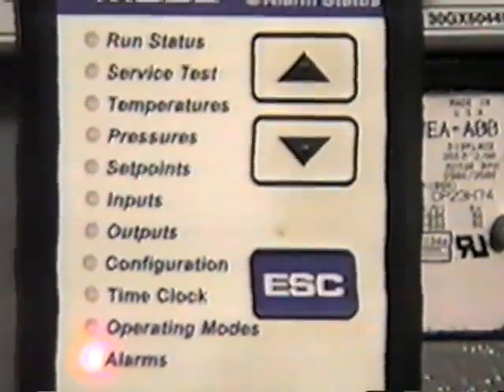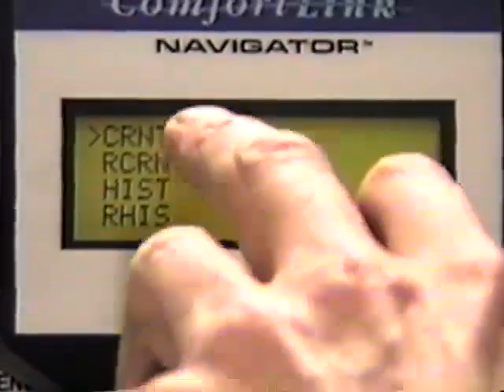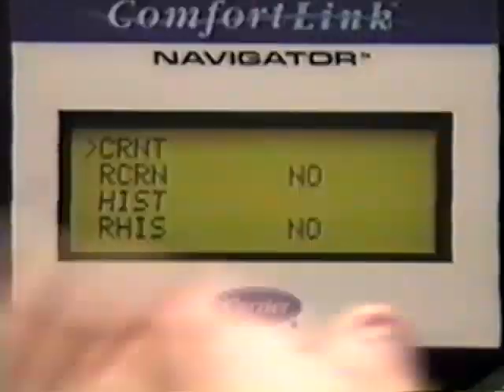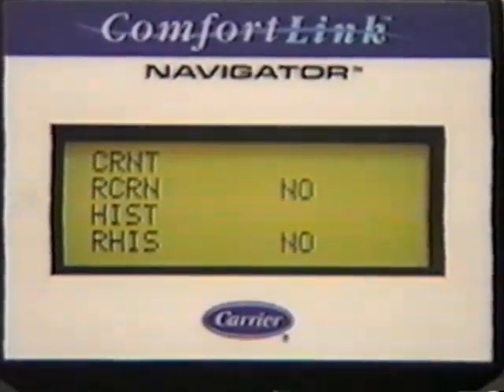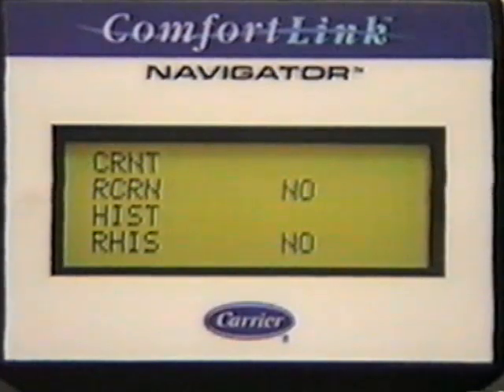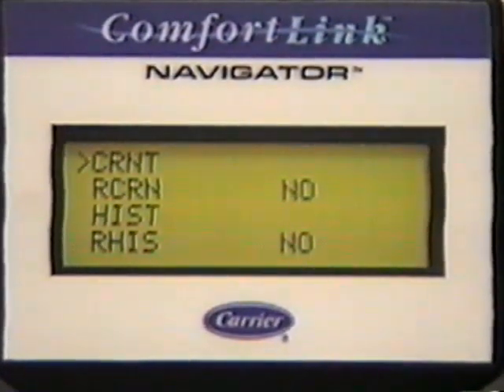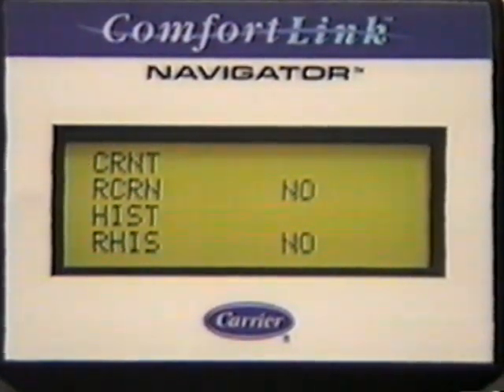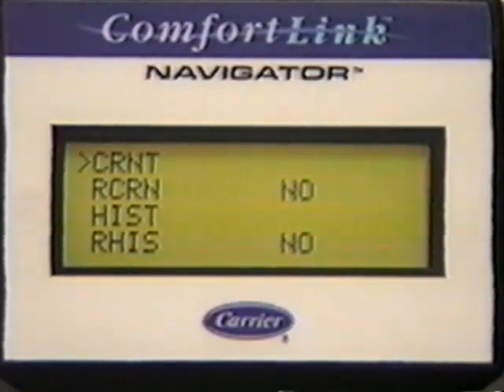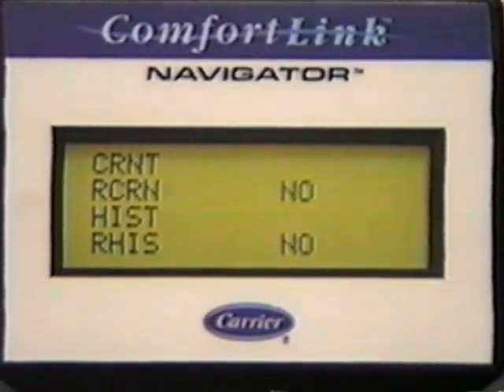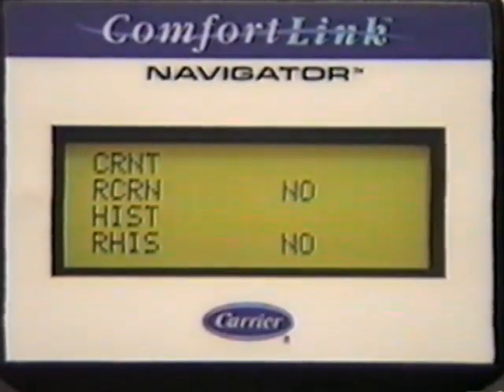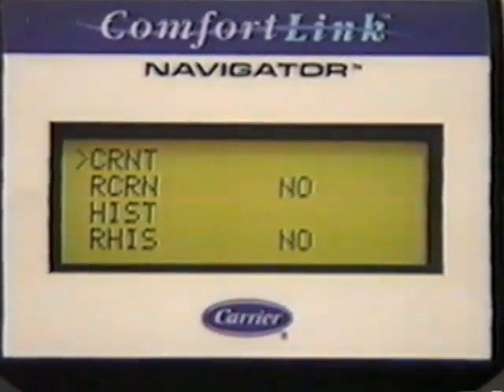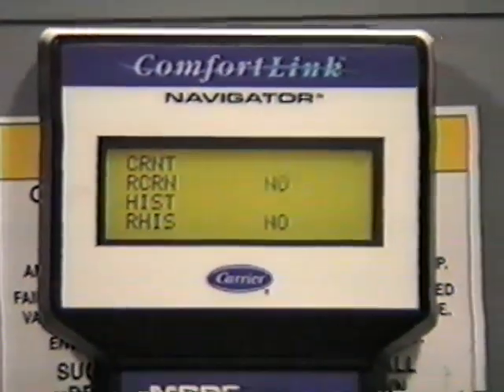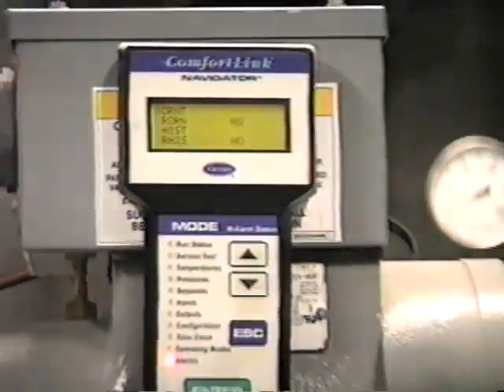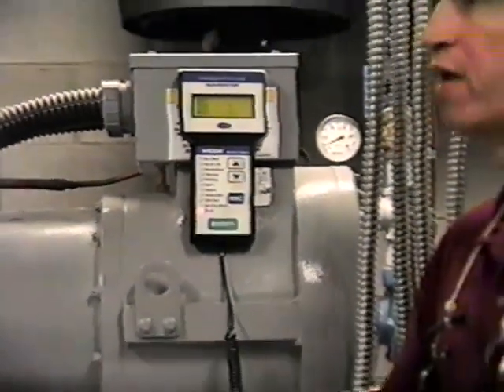So you go into this screen, and you'll see a particular number there. It'll say T051 or any one of those listed in your manual as far as possible alarms or alerts. At that point, you hit both keys at the same time, and it'll tell you exactly what it is. At that point, you have to find out what it is, correct the cause of it if you can, or call somebody that can help you correct the cause of it. And then you can clear it.